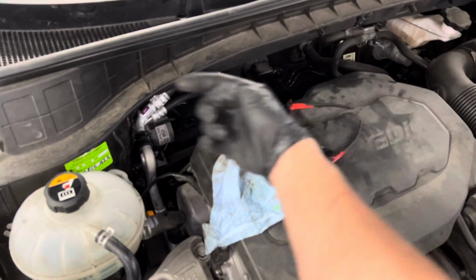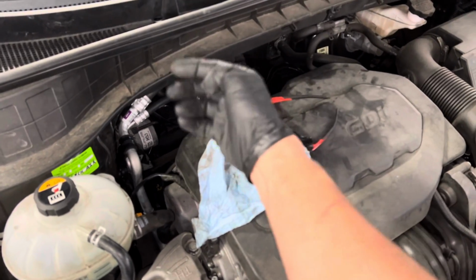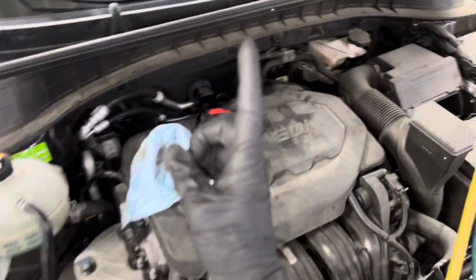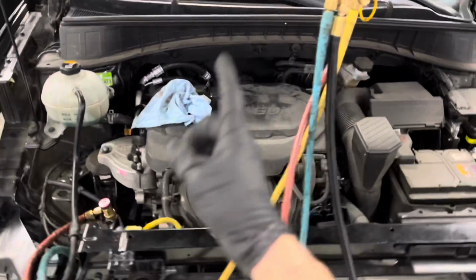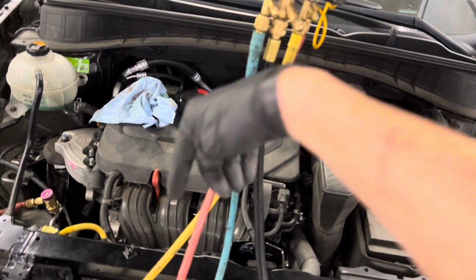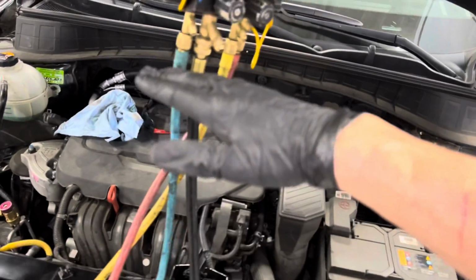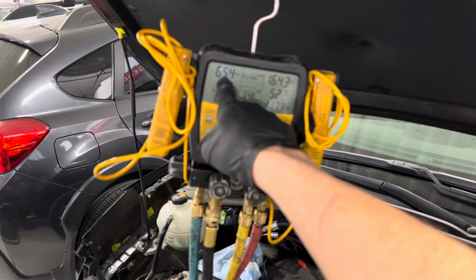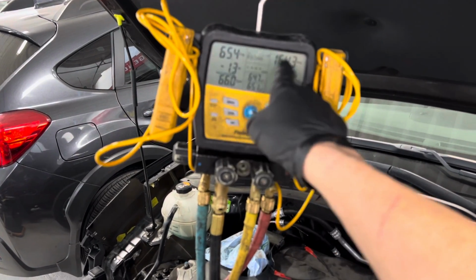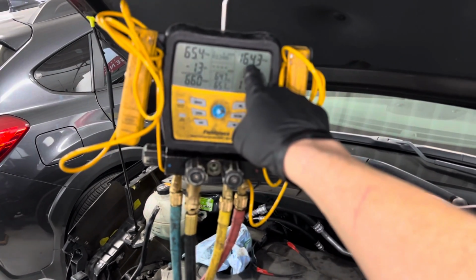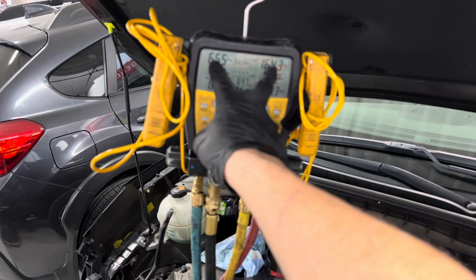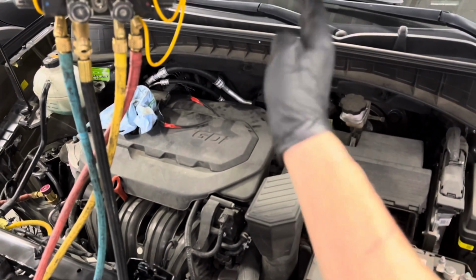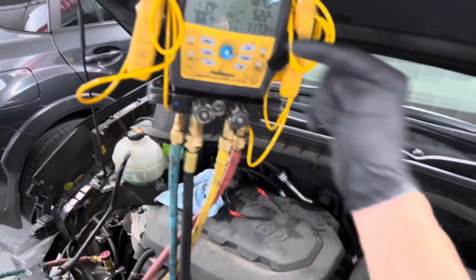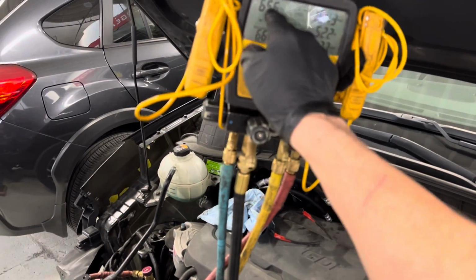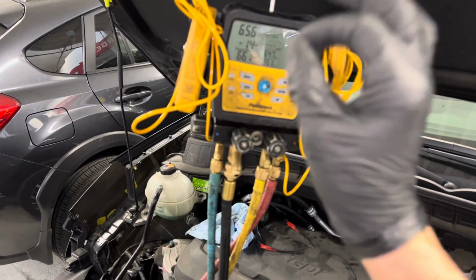So it allowed nitrogen to freely flow until there was 100 psi difference between the low side and the high side, and then the pintle drove all the way down, and it stopped the flow. And this is the evidence right here. Here's 160, basically we're 165, 164. So you have 100 psi difference between the high side and the low side because the expansion valve is stopping any more dry nitrogen from flowing through the expansion valve to even get to the low side. You must understand your differential.